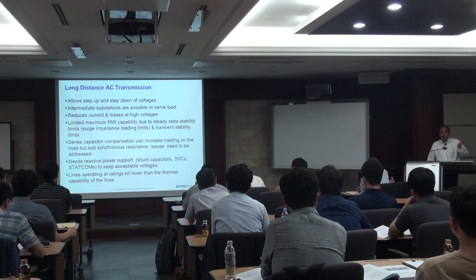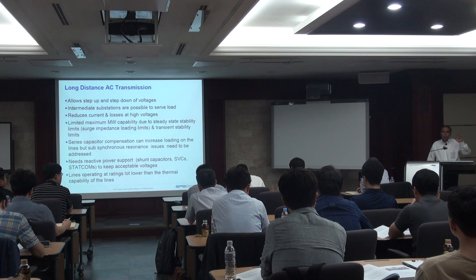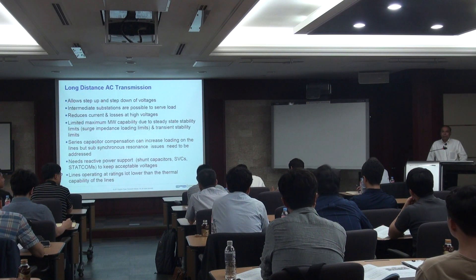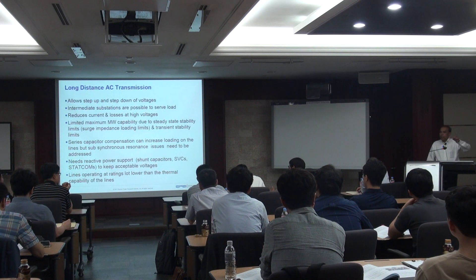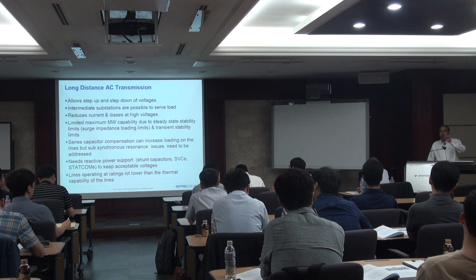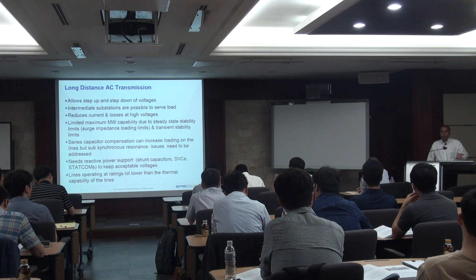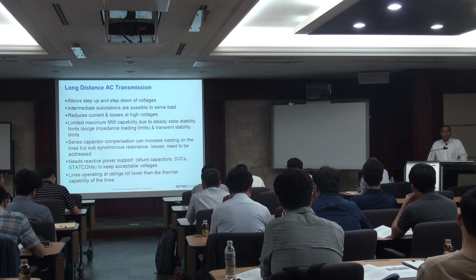We use a step-up transformer to a higher voltage for transmission. For the same power, voltage times current times power factor equals power. If you increase the voltage for the same amount of power, the current will be reduced, so the I²R or I²X losses will be lower. That is why we want to transmit at a higher voltage.